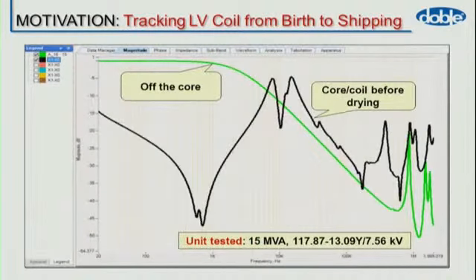We take a coil, we measure it, it's in green. You add the core. If you look at the green trace, it's just a pure inductance. It's what you expect. As you get to higher frequencies, as capacitances kick in, you get a different response. The one in black is when you've added a core. That's a 3-phase unit. You can tell because of the low frequency response. There are 2 resonances around about 2 kilohertz, 1 kilohertz.